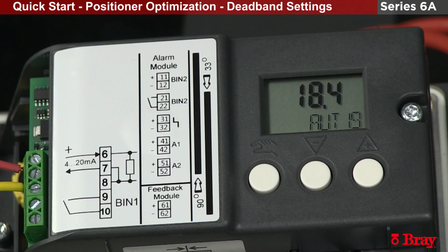After you commission your 6A positioner, if you find you're having issues with chattering once the valve has reached this position, or sometimes people call it hunting, where the valve is looking for a certain position, this may be because the deadband is too tight for the application. We can increase the tolerance of the deadband through the programming of the 6A for better performance in the field.